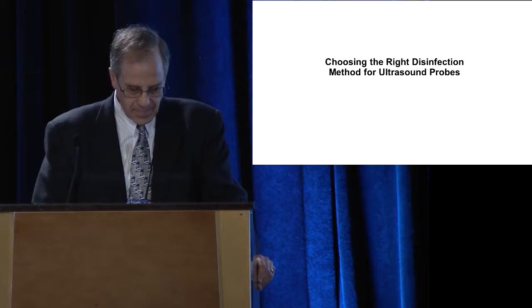So you need to choose the right disinfection method for ultrasound probes. We look back at the Spaulding criteria, which is the globally adopted system. Disinfection of medical devices or surfaces depends on its intended use. We just heard a lot about that. Each disinfection level is defined by a specific pathogen activity spectrum. You can see here the little tables. We have the critical, the semi-critical, and the non-critical classifications. Again, sterile tissue or blood, mucous membranes or non-intact skin, or healthy intact skin. The level of disinfection for critical is sterilization, for semi-critical is high-level disinfection, and for non-critical, low-level disinfection.